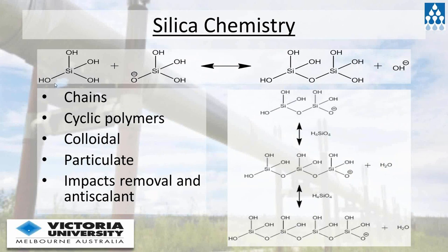Silica in water exists primarily in groundwater as monosilicic acid, or the silica monomer, as I'll be calling it. It can exist on its own as a non-ionic material at a pH below about 9. It starts ionizing above 9, and you end up with the monovalent anion. There is also a divalent anion that becomes more important as you go even higher. Now, when you get these two species together, and you can also get it with the non-ionic form, you see dimerization, a chemical interaction where you end up with the dimer of the silica.